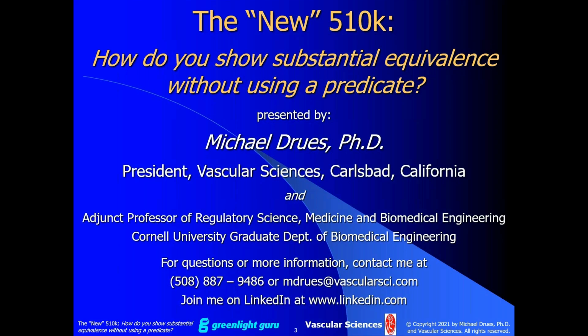I mean, there's an infinite number of possibilities here, but the first thing that I would be doing in that case, Brandon, is going back to the FDA and making sure I have a good understanding of why they're saying no. If they're saying no because we don't see this as a class 2 device, now you might be looking at potentially a class 3, a PMA, or maybe an HDE. So we have to find out. It's not sufficient, and you should not let FDA get away with simply saying no and nothing else. They have to give you a reason or reasons why.